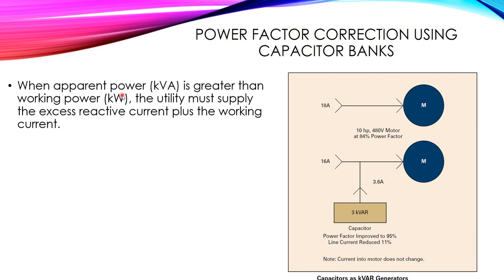When the apparent power in kilovolt-amperes is greater than the working power in kilowatts, this means our apparent power contains both active and reactive power, and the utility must supply the excess reactive current. We have Ia representing the active power current and Iq representing the reactive power current, so the excess reactive current must pass through the transmission line in addition to the active current.